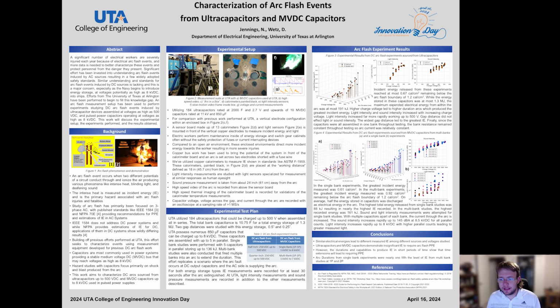Ultracapacitors and MVDC capacitors demonstrate insignificant energy to recommend any personal protective equipment. However, if the durations were extended out to 2 seconds, this would be extremely drastic, and the personal protective equipment required for workers in the event that an arc lasts 2 seconds or greater would need to be equipment rated for incident energy applications.